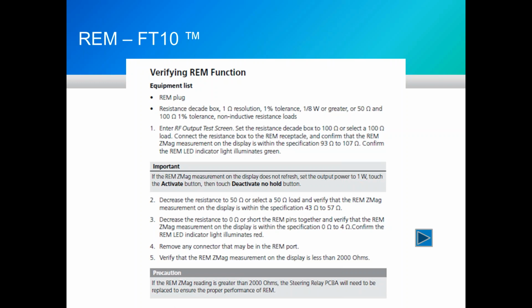And we would also look for a 40% increase. So if we set a load resistance of say 60 ohms, reconnected that REM circuit to the generator, we would expect an alarm around 82 ohms or so, because the Triad and earlier units would alarm two ways. One, if a maximum or minimum resistance was reached, or if we saw a 40% increase in resistance. With the FT10, we do this very much differently.